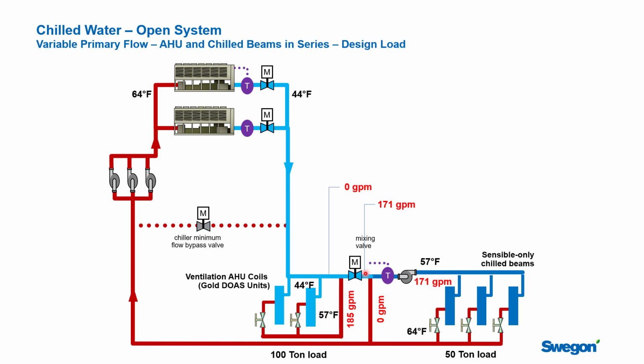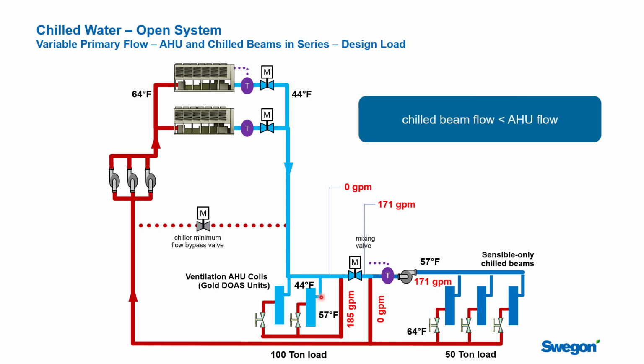And when you do that, you're now going to lose control here, because obviously this valve is going to be able to block this pipe. And what will happen here is that you will not be able to get the 185 GPM you need through these coils. These valves will open, but this one will close. And so you will not be able to do the dehumidification. What happened in here was we broke the rule, right? Now the chill beam flow is less than the air handling unit flow.